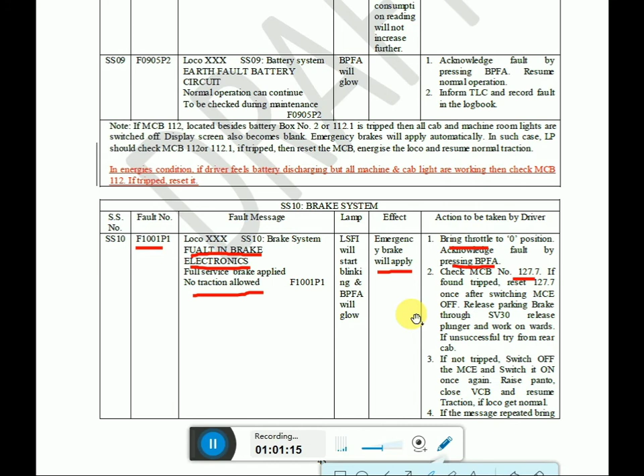Check MCB 127.7 in SB2 panel. Brake electronics for pneumatic MCB available in SB2 panel. If it is tripped, reset. If it is in good condition, it is okay. Recycle the MCB, means 2 or 3 times on and off and try.